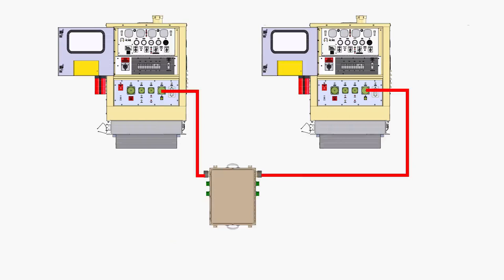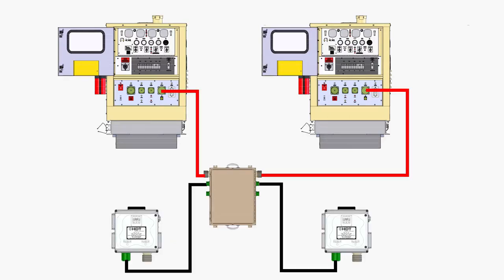Now attach the 100 amp cables. You can connect utility distribution boxes and other loads at this time. Next attach the signal interconnect or parallel cable to J6.